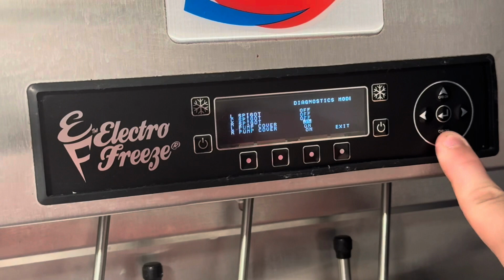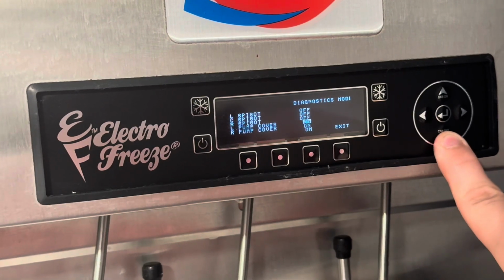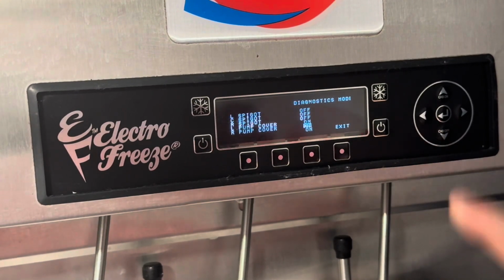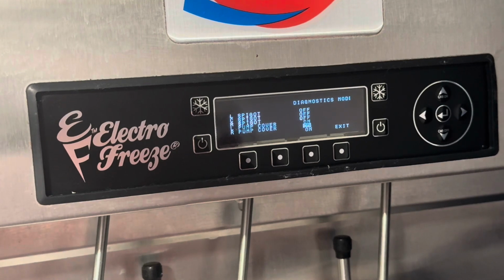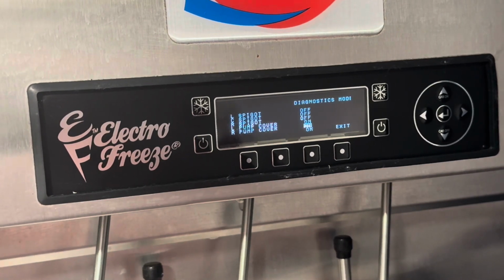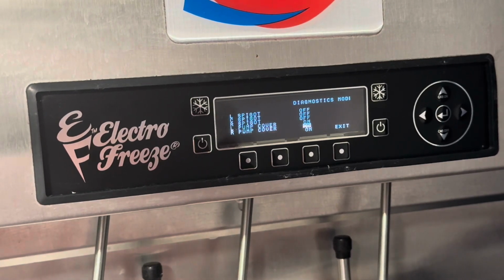These are our pump covers. So we have both pump covers on this machine, so they both are on. Now if you have a cover that's on the machine and is correctly installed and this reads off, you're going to either have a sensor failure or a wiring failure.